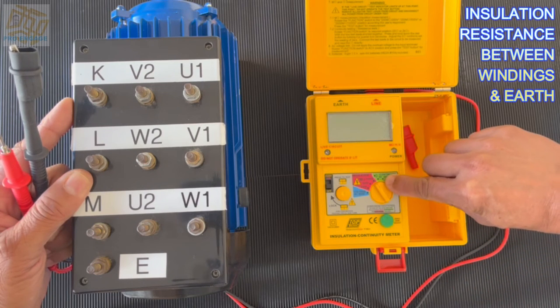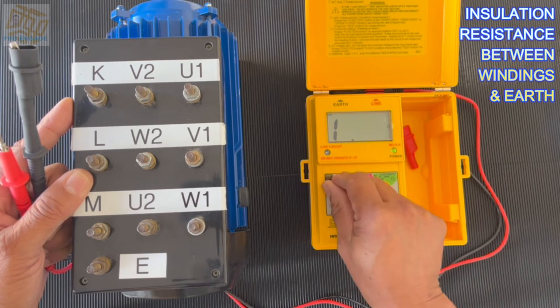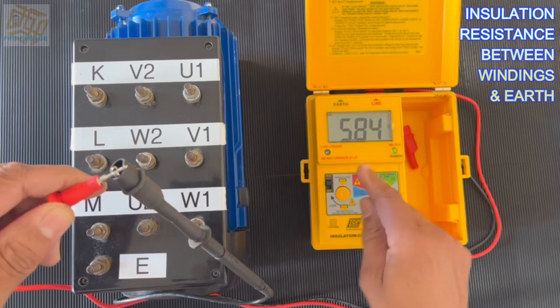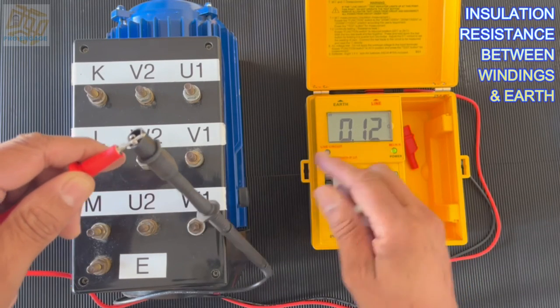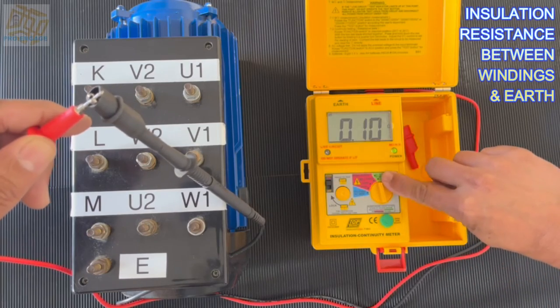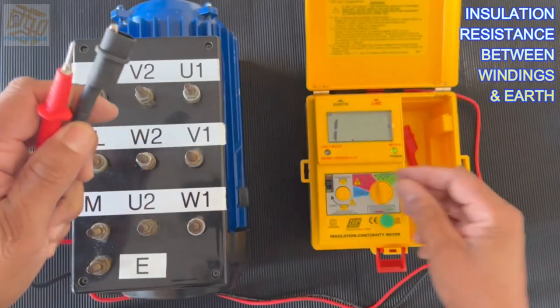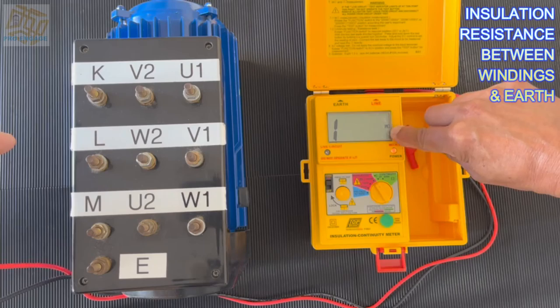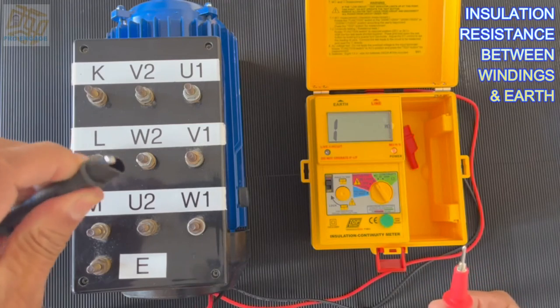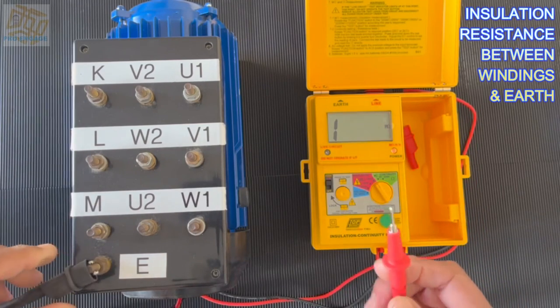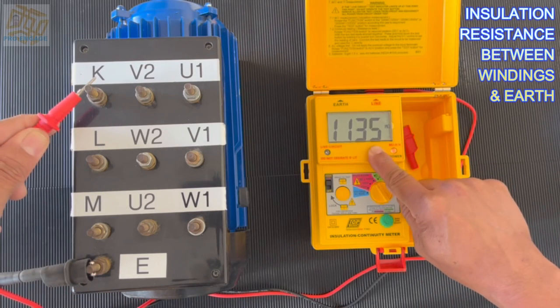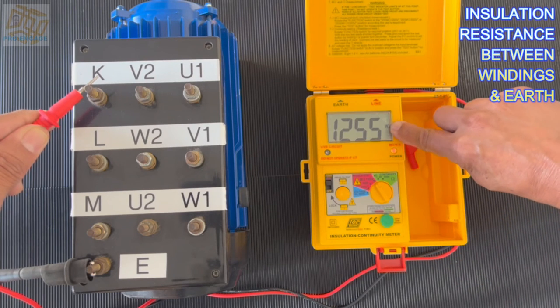So we will put the meter on. We've got our ohm scale there and we're going to just test and see if the battery is good. It doesn't have a battery test but there is a green light on the right. And if I check the leads it should go to zero. That also means contact. So even on the mega ohm scale if there's contact it would move towards zero, which is bad. We want that reading on the screen, no contact, one representing in this case infinity. So I put my crocodile clip on the earth. I test.